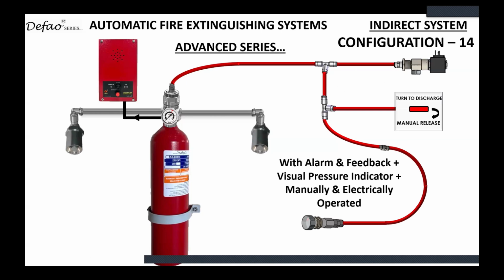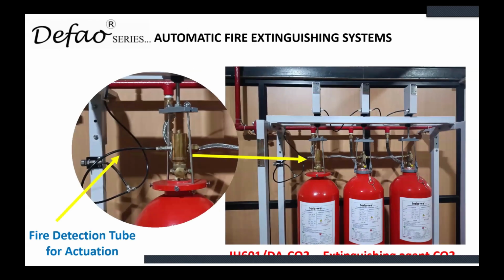It is scalable, and it can also be integrated with your existing fire alarm system. So the scalable options are almost infinite. So this is one condition where a tubing system was connected to a bigger system. We're talking about three 45 kg CO2 systems. And in case of fire detection by the tubing system, all three cylinders will be triggered instantaneously.